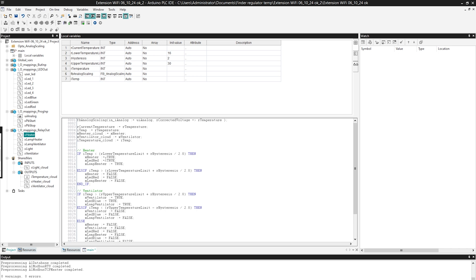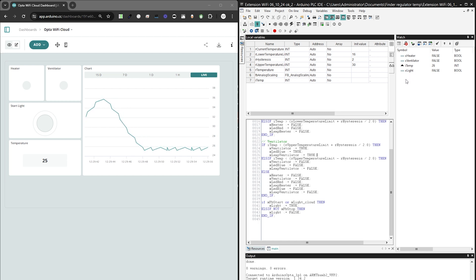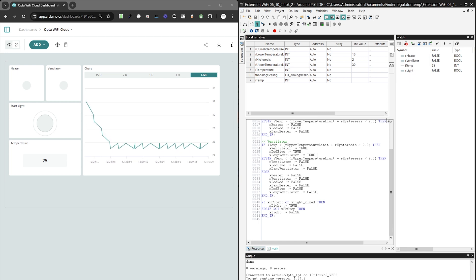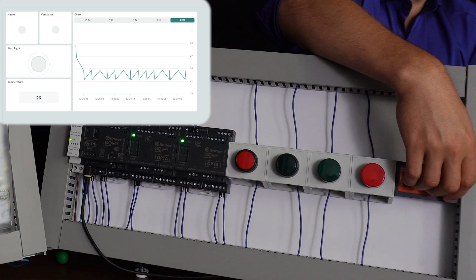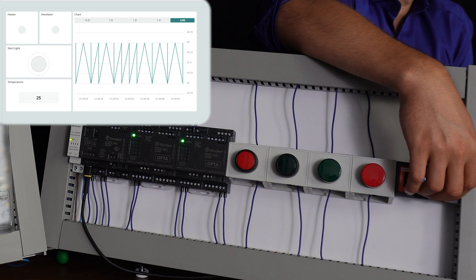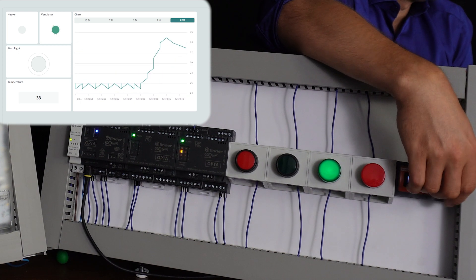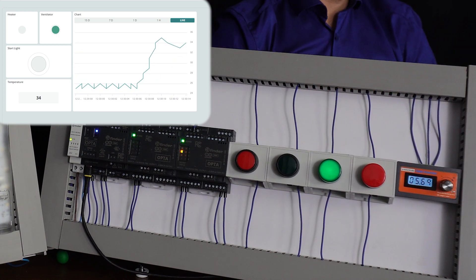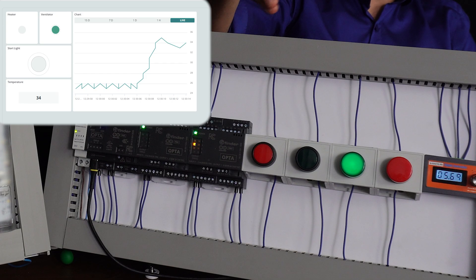Let's move on to testing this program. I uploaded the program to the controller. In the watch table I monitor several variables: heater, ventilator, lighting, and current temperature. I will try to exceed the temperature above 30 degrees — the ventilator should turn on. The temperature is about 35 degrees, the ventilator is on, indicated by the green light connected to the controller.